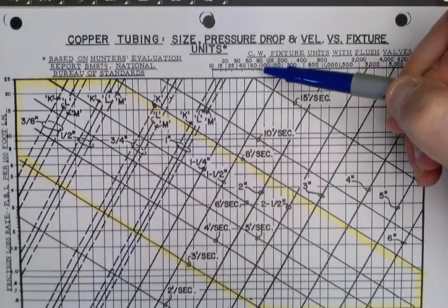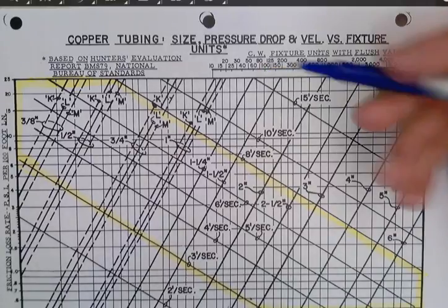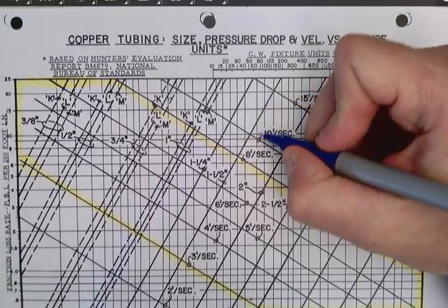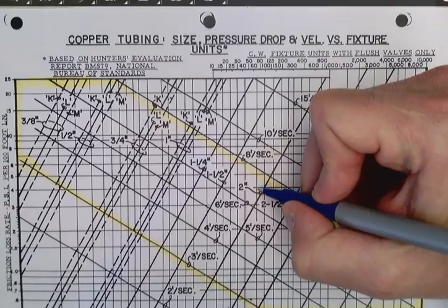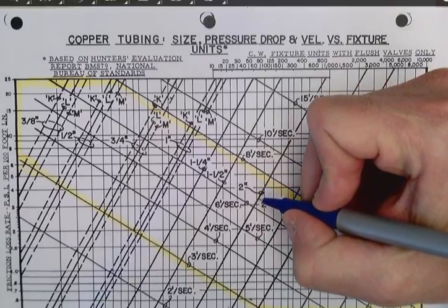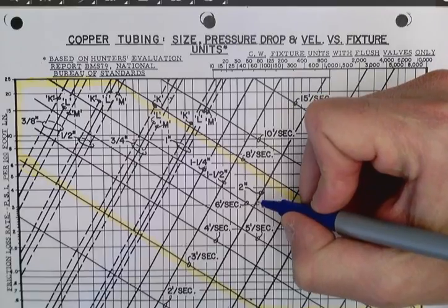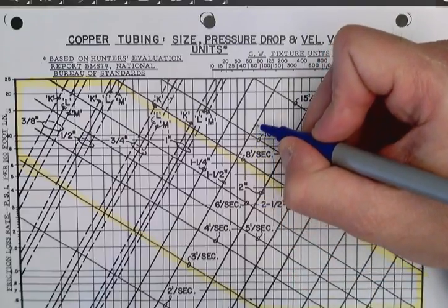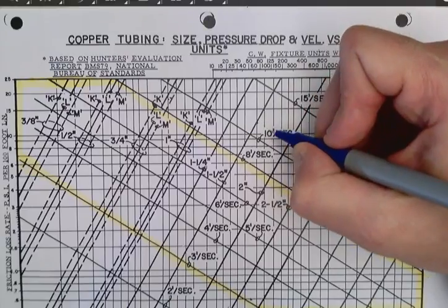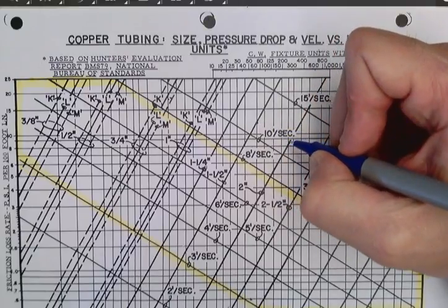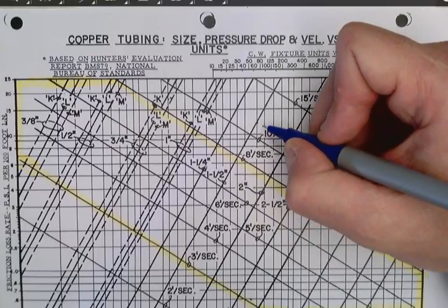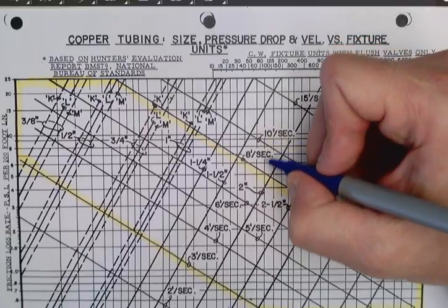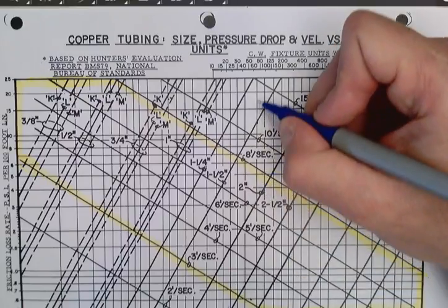So up above, whenever we're looking at 60, basically what we want to do is work our way down, and we want to fall somewhere within the range of the yellow highlighted velocities. Whenever I do that, I end up falling onto the 2 inch line. If I were going to use 1 1/2 inch, I would be all the way up near 10 feet, 12 feet per second where it intersects, and that's just too high of a velocity. So we're going to stick with the 2 inch line size for the 64.5 fixture units.